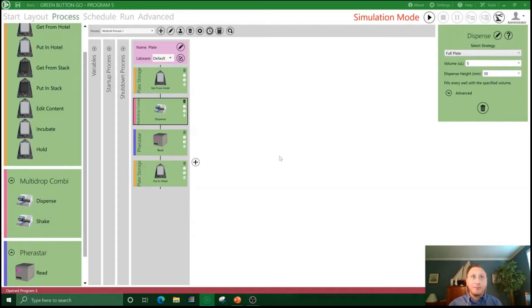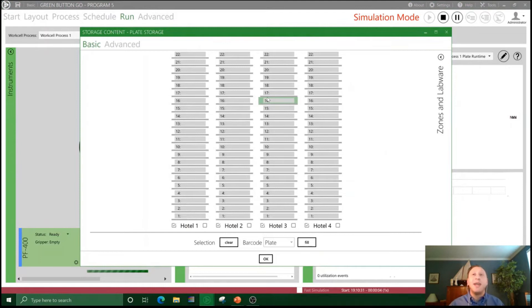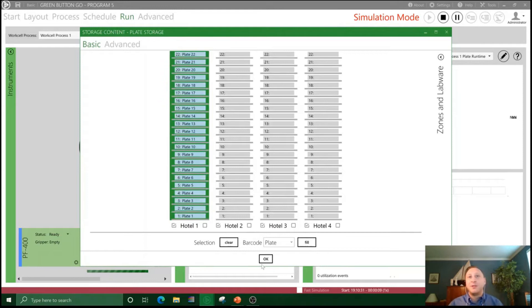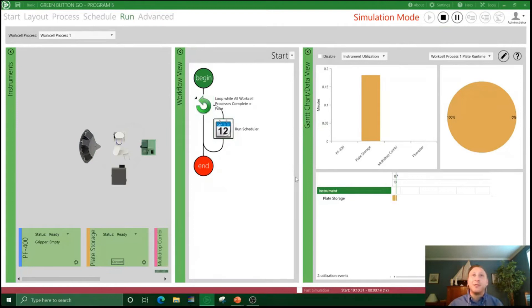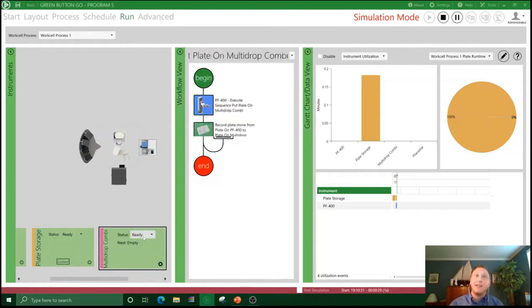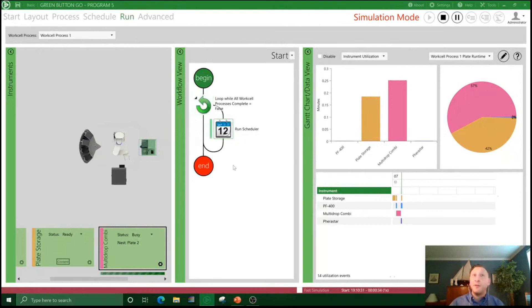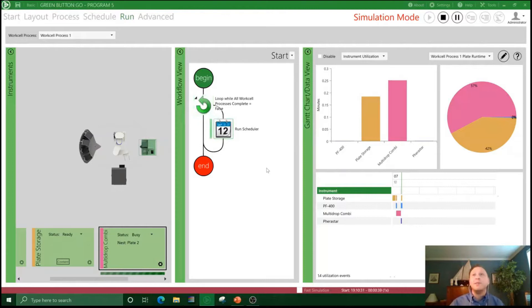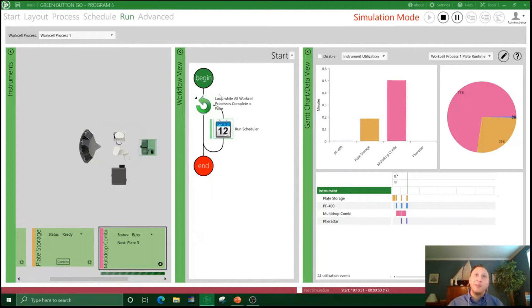Now that we've set that up, we can move into our run screen, and we can start the process. The first thing that we see is we're prompted to add plates. This is automatic. In this case, I'll fill one hotel with plates for demonstration. And now we're off to the races and running. As we can see, the instruments that are currently in use are highlighted in green. This here is a mimic of the same layout that we developed in our layout tab. Clicking on instrumentation allows us a very quick and easy view of what plate is currently in the nest. In the center of the screen, we see the workflow view. What this is is a glimpse into the lower level advanced processes being executed by Green Button Go.